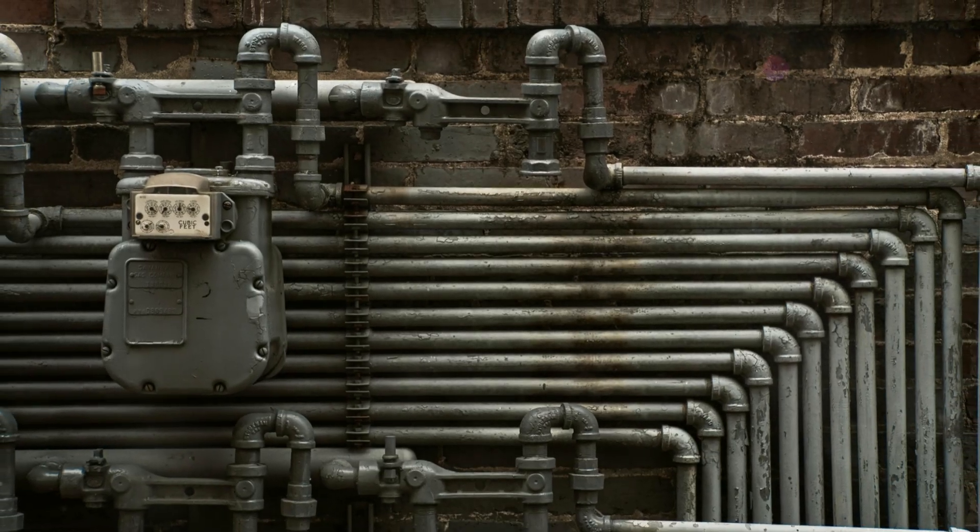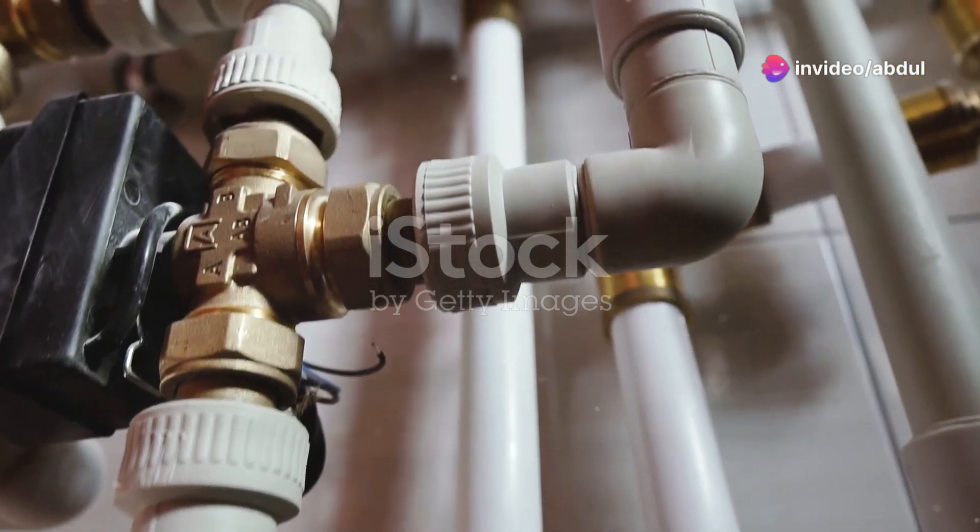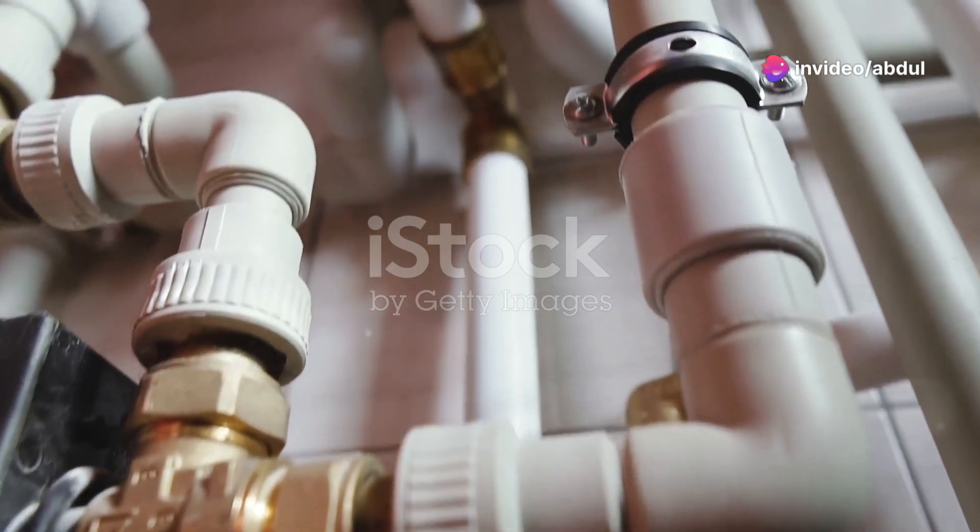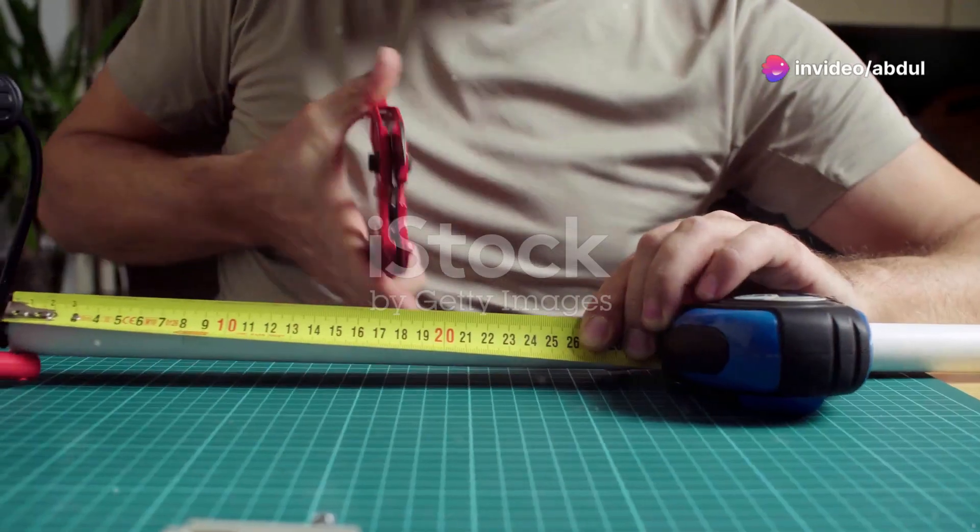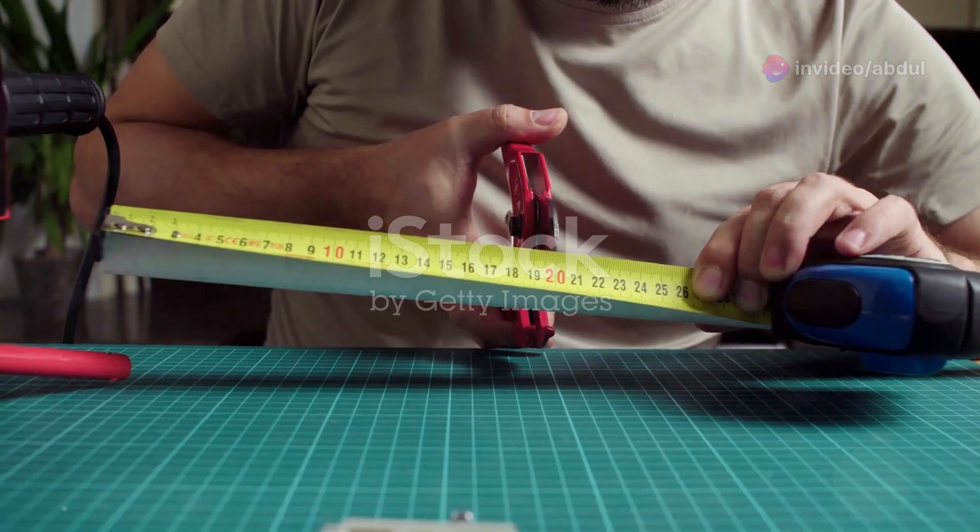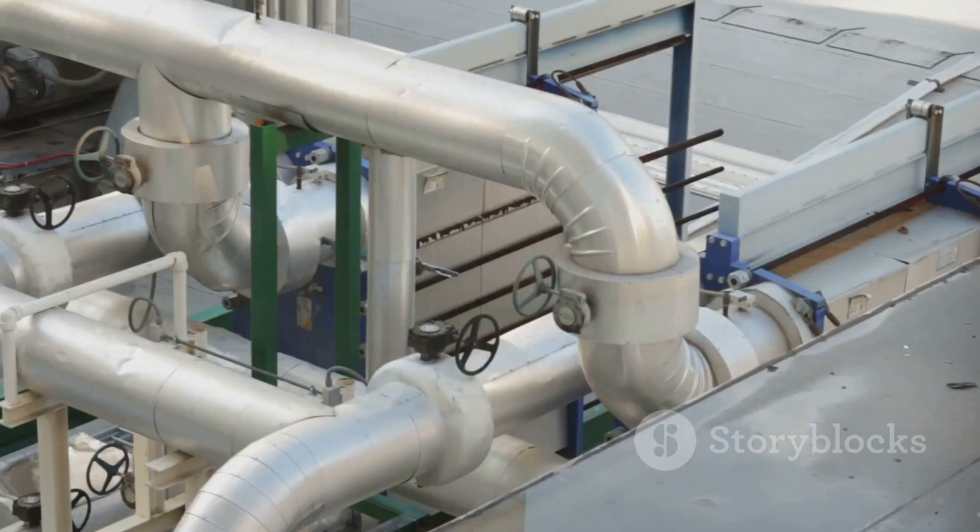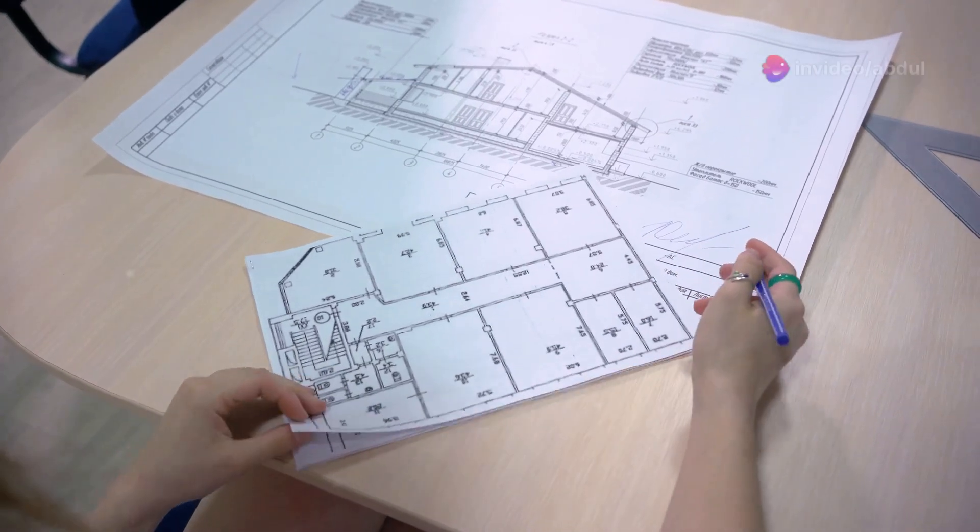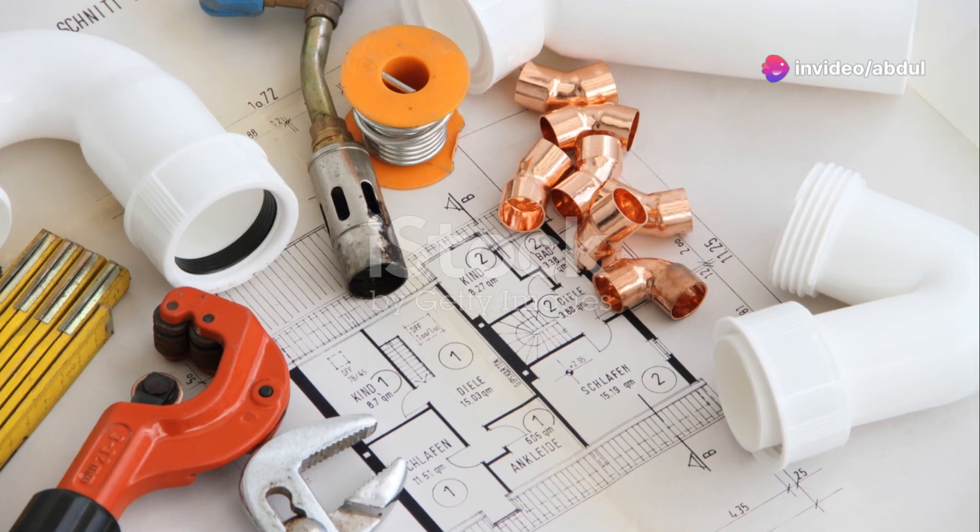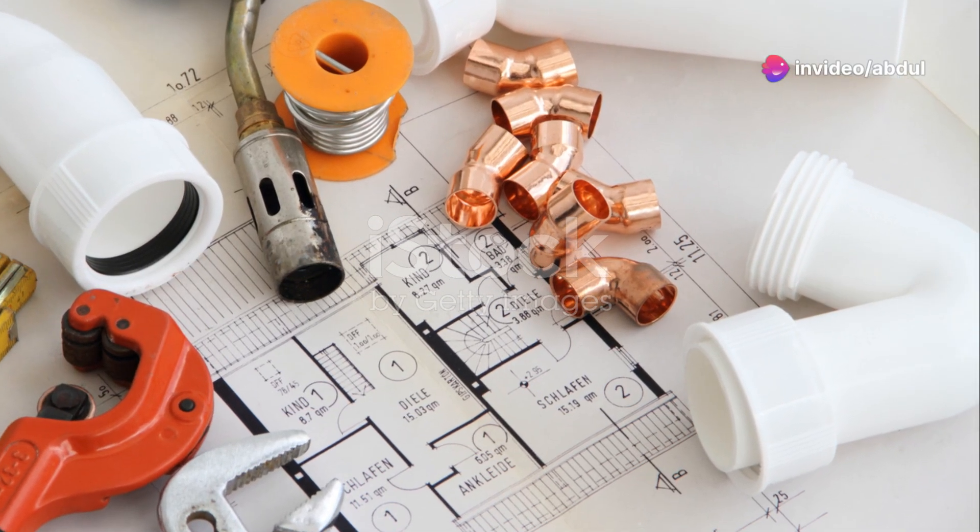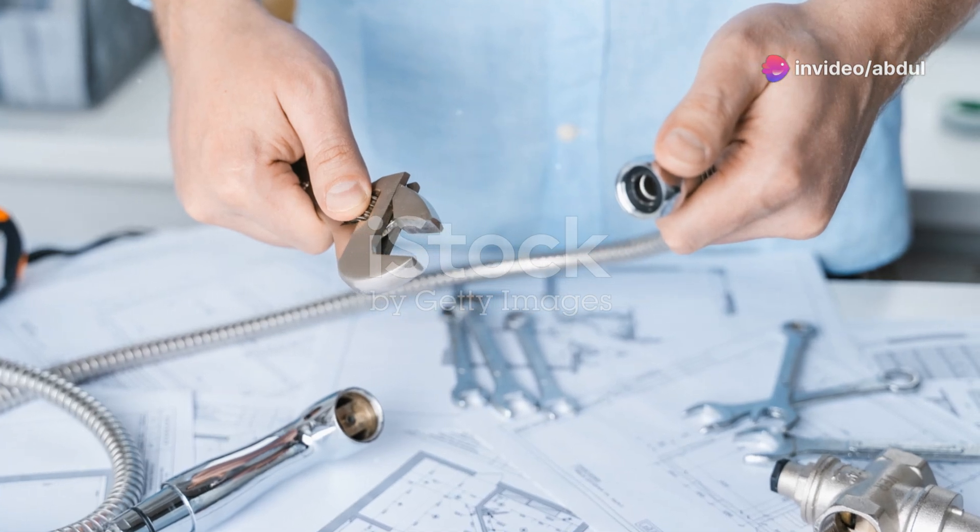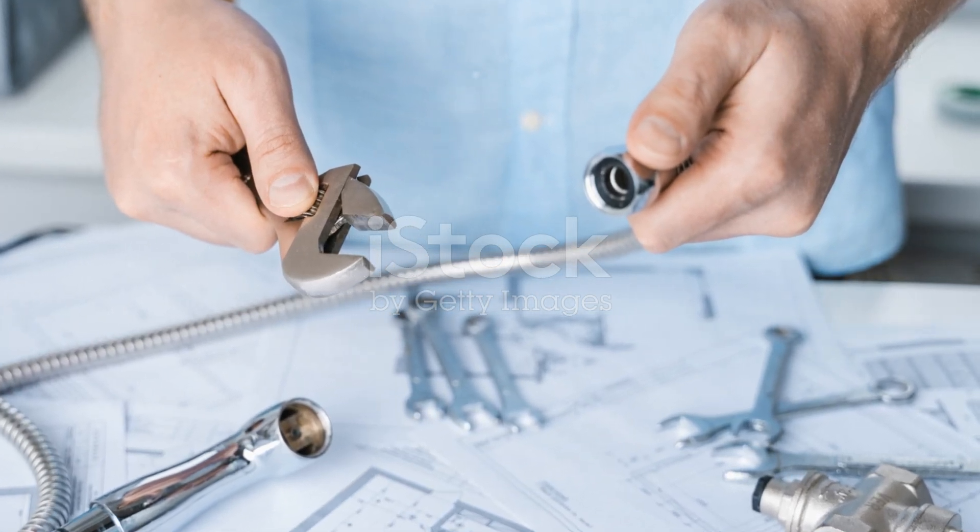First, double-check that all fixtures are properly connected to both the water supply and drainage systems. Ensure that all lines have the correct slope and diameter. Verify that vent lines are properly connected and routed to the exterior. Next, review your annotations and dimensions. Ensure that all fixtures and components are clearly labeled. Confirm that all dimensions are accurate and placed in logical locations.